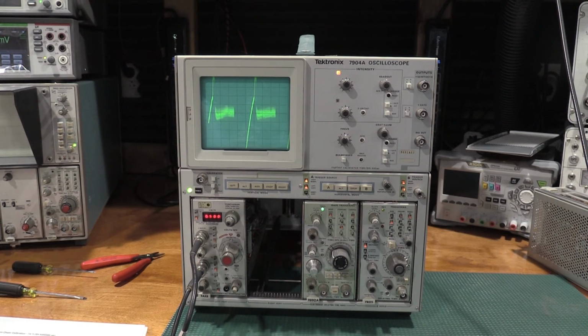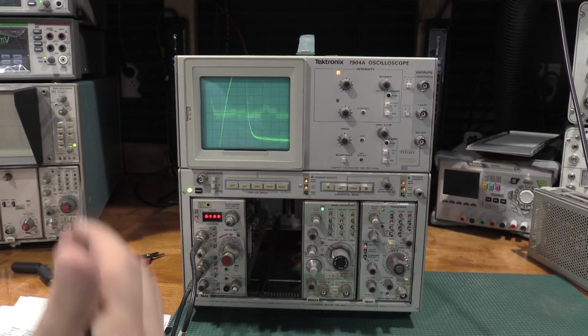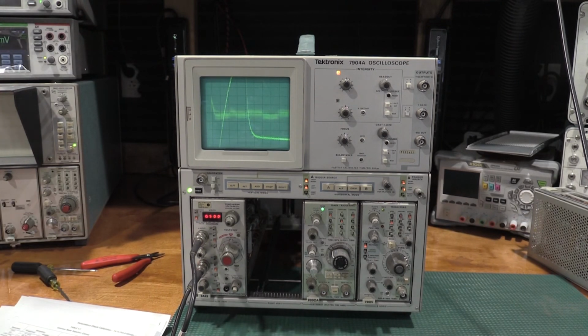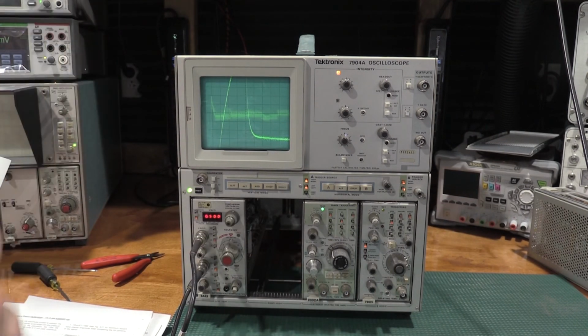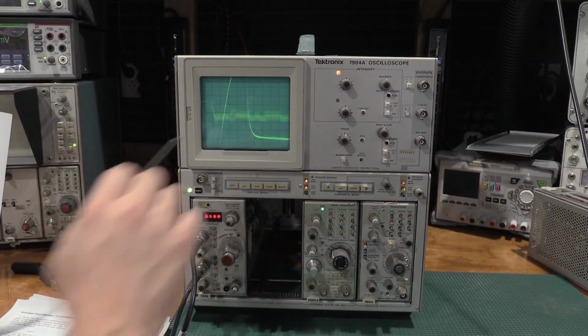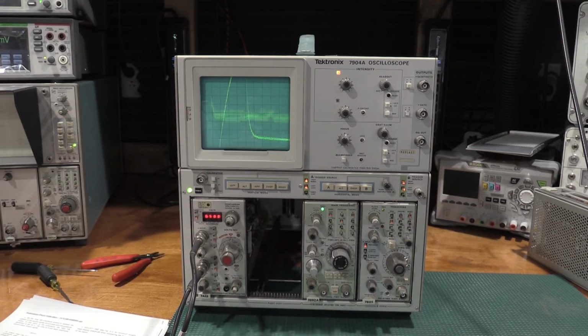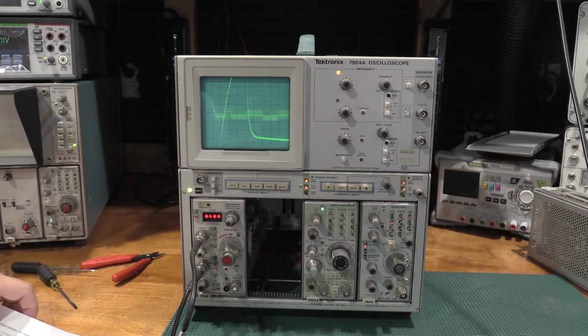I do want to adjust R28B. Well, it seems my unit doesn't have an R28B. I did find an R28G, but I just don't want to tweak that and say that's it. However, I did notice my 106 was set wrong. I had it set to 1 kilohertz, and I set it down to 100 hertz, and it cleaned it up significantly. So it's looking like it's pretty close. Very difficult to measure, but it is looking pretty good. So we'll check 10 kilohertz now and see where we go.